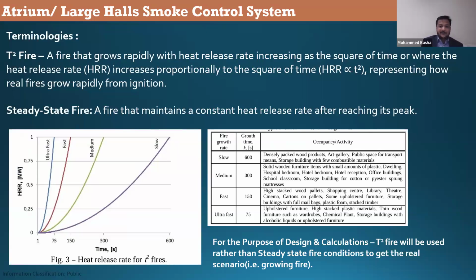Let us see steady state fire first. What is it? A fire that maintains a constant heat release rate after reaching its peak. This is like a burner, okay? Like a candle, you can say. You start a fire and the candle will continue to release the same amount of heat until the candle loses its mass, right? There is no difference in the heat release rate, the amount of energy it is producing. It will be like 10 kilowatts at the beginning. At the end of the candle also, you will have the same 10 kilowatts. This is called steady state fire.